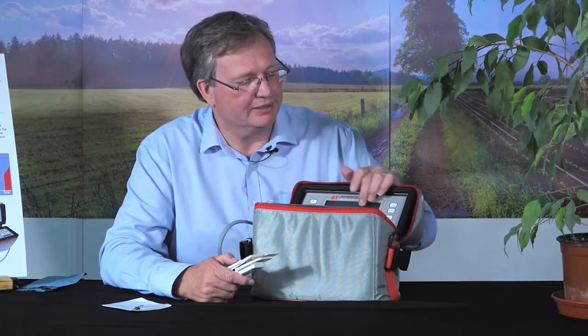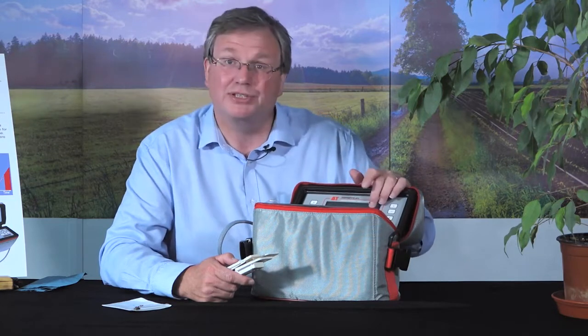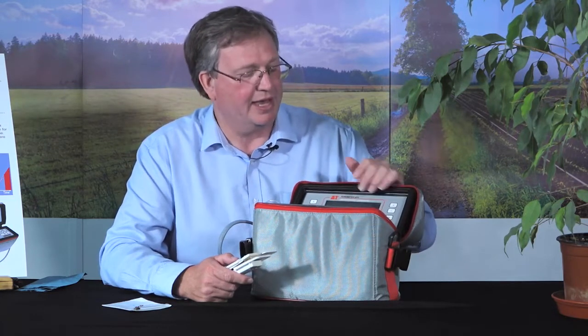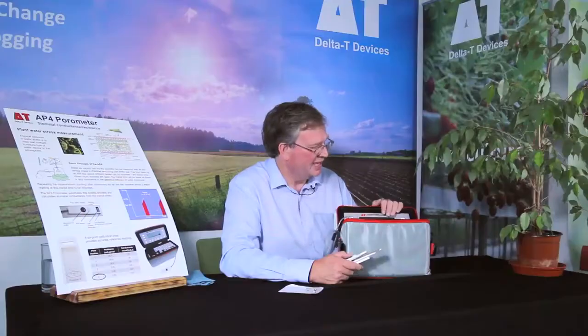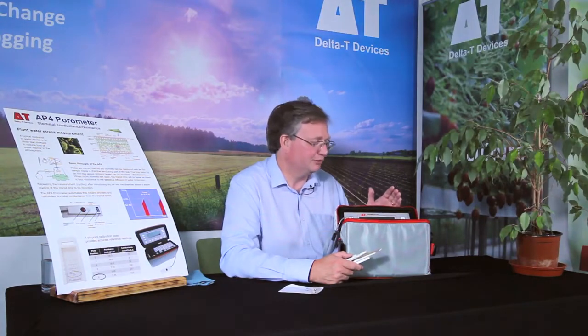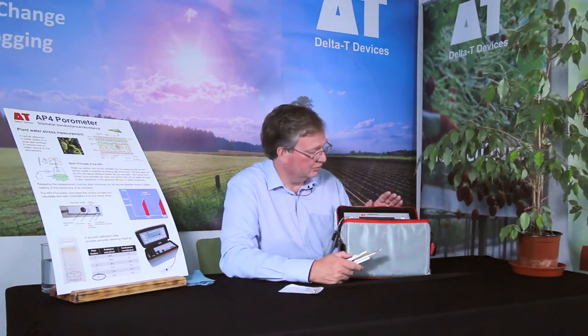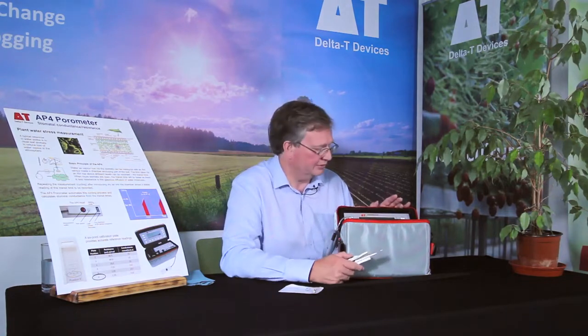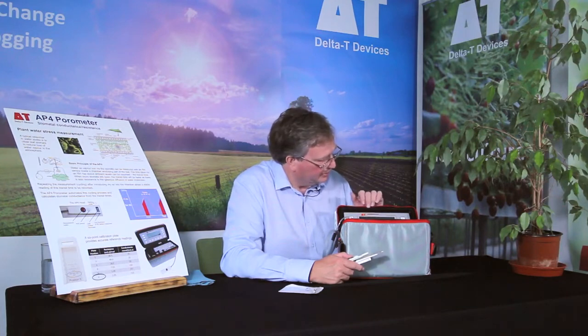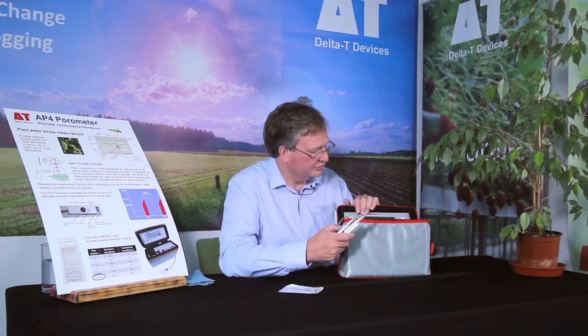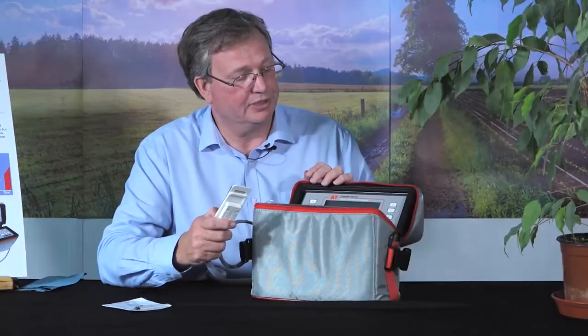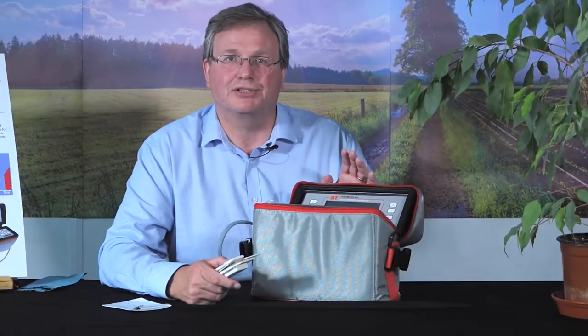And then I will redo that particular value on the plate, which you have the option to do, and try and fit the curve again. If it's above 10%, you can redo some points, but I would tend to repeat the whole calibration process. It doesn't take too long, and it's always good to get a good calibration so that you know you're going to get the best measurement of your leaves. So I'm happy with this error value here, so I'm going to install this into the Porometer, and then I'm ready to take some leaf measurements.